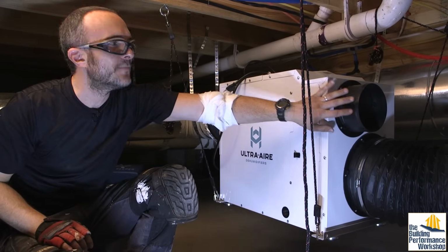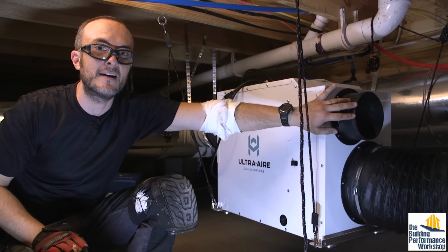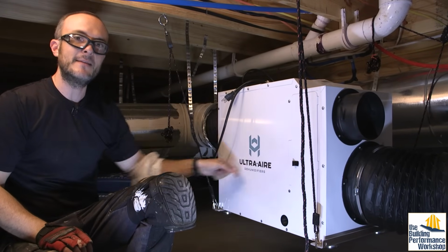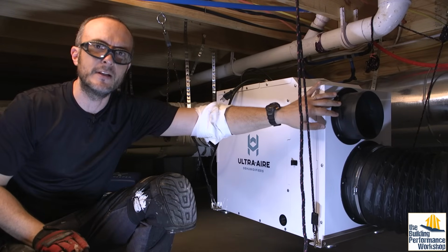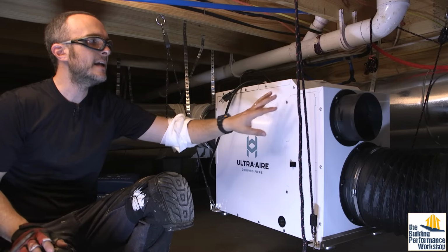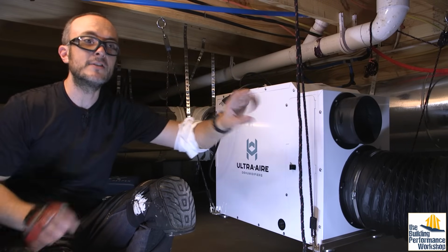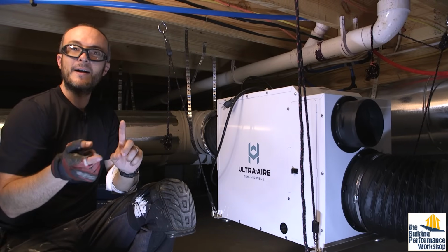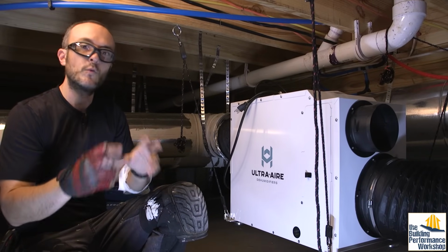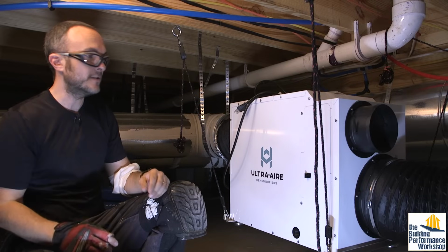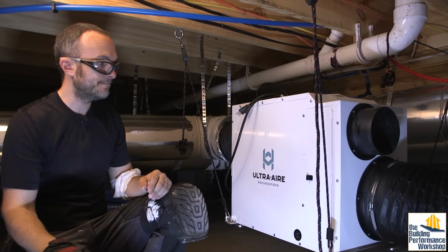Normally in an Ultra-Aire system, this is for introducing outdoor air and then dehumidifying it immediately before you distribute fresh air throughout the house. That's called supply-only ventilation. That'll slightly pressurize the house. That's fine. In this case, I would use it to introduce some very refined intentional pressure imbalances within my house, which is a useful thing to do, and you can see more videos about that on our channel.